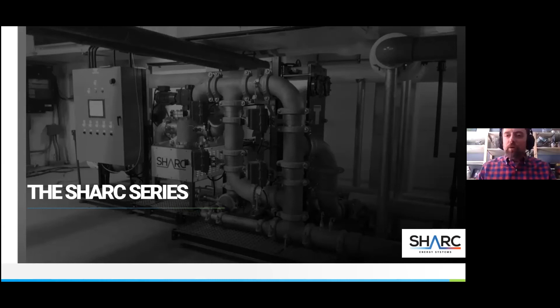For the larger series, the Sharc series, mainly designed for our larger flows, there's a lot of attention in the district and district utility side of things. So electric heat pumps provide the heating, cooling, and hot water when they're combined with the Sharc. This again aligns with any of your electrification initiatives. There's zero fossil fuel consumption, and it can be powered by on-site solar PV. Also, when we're rejecting heat to the wastewater source, we're able to reduce or eliminate the run times on cooling towers, which anybody who's been around cooling towers knows consume tremendous amounts of fresh water.